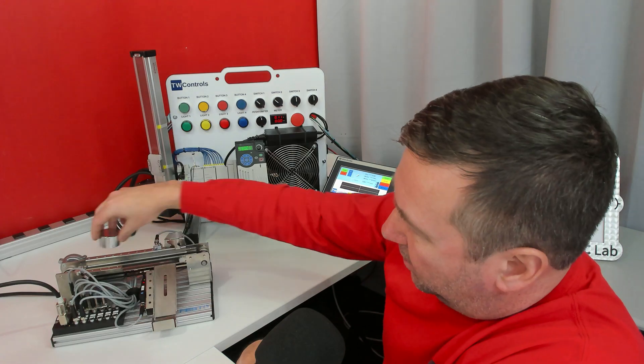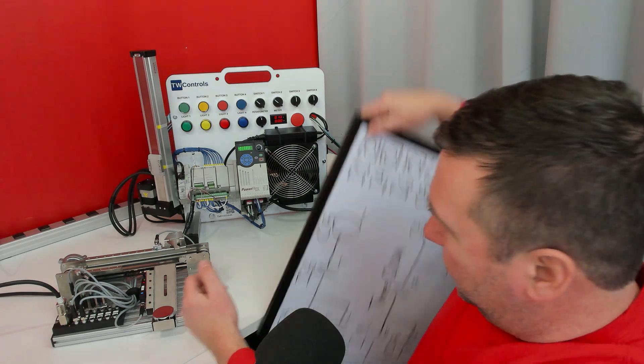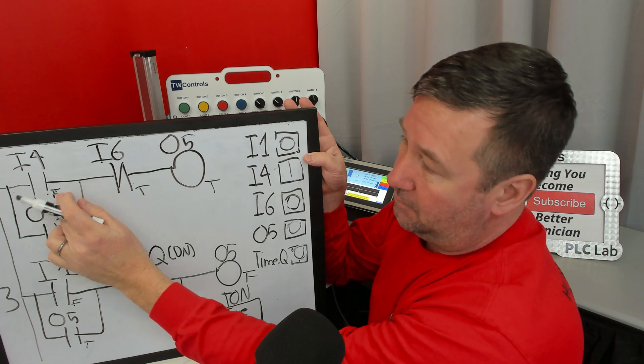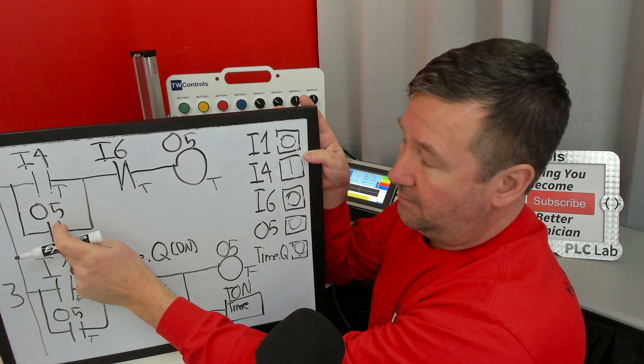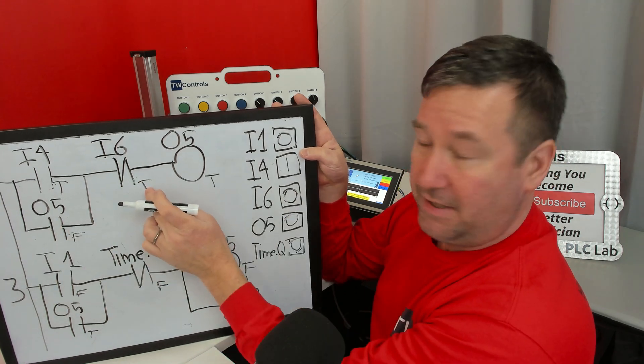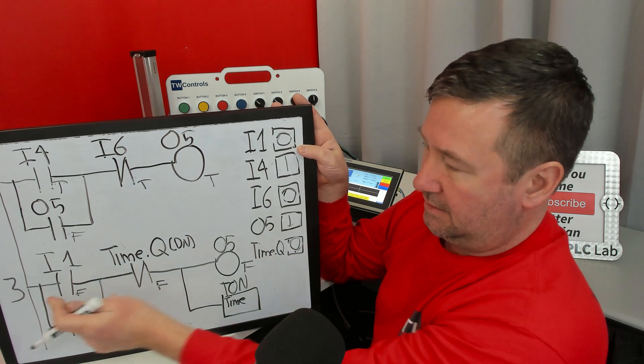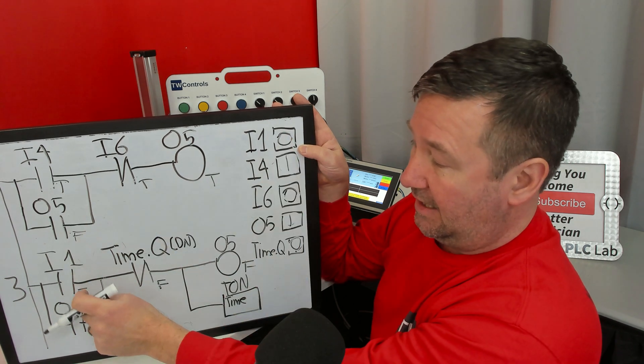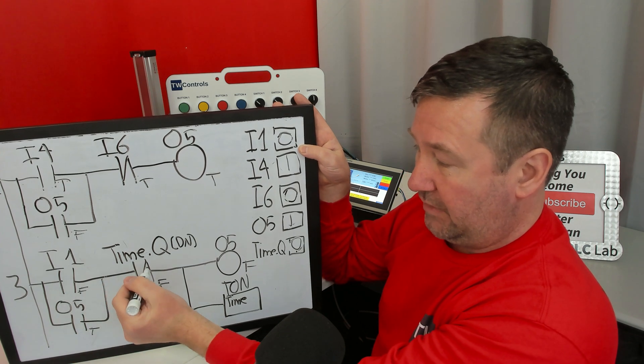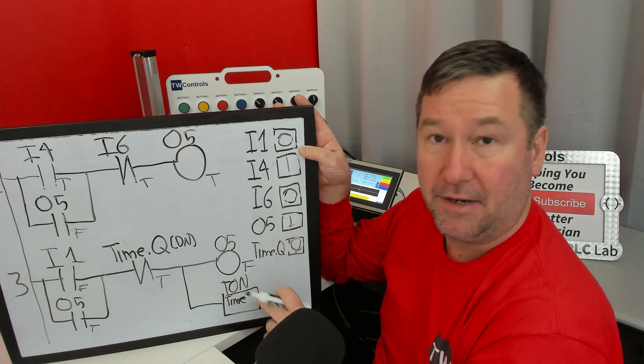The next question I always like to ask is: what's going to happen if I press my green button? I'm going to put a part not at the part present, just something you can see. I hit my green button and the conveyor starts. So we pressed our button - it puts a one at input 4. This instruction looks for a one at input 4 - now it will be true. This instruction looks for a one at output 5 - it does not have one, so at this very moment this is false. This looks for a zero at input 6, so it is true. I do have a continuous path of trues, so this output energize will be true and writes a one to output 5. Now rung 3's instruction looks for a one at output 5 - rung 1 did write a one to it, so it is true. This looks for a zero at the Q - it does not have one, so it's true. That makes our output energize true and our timer times again.